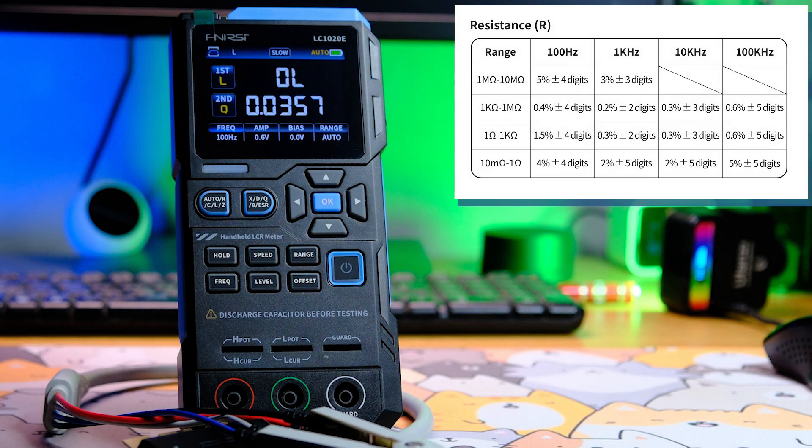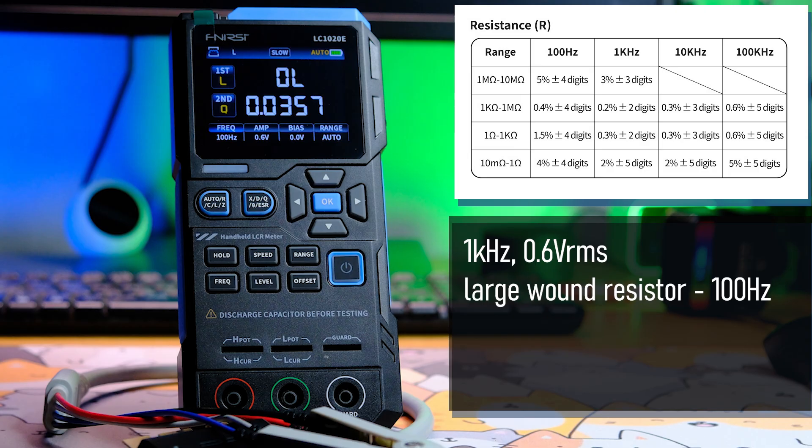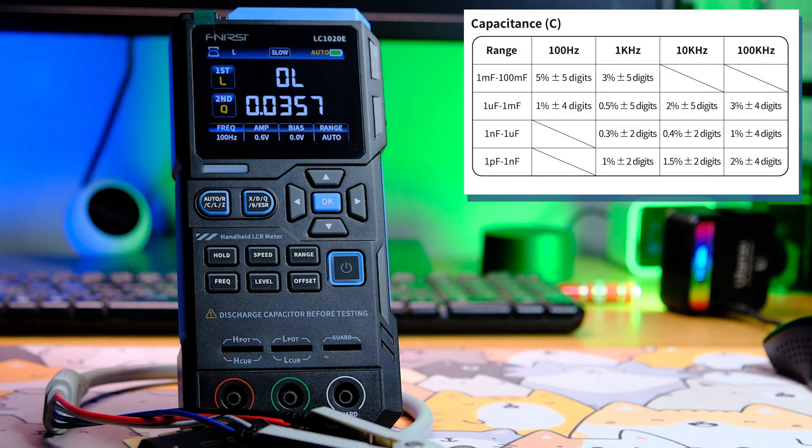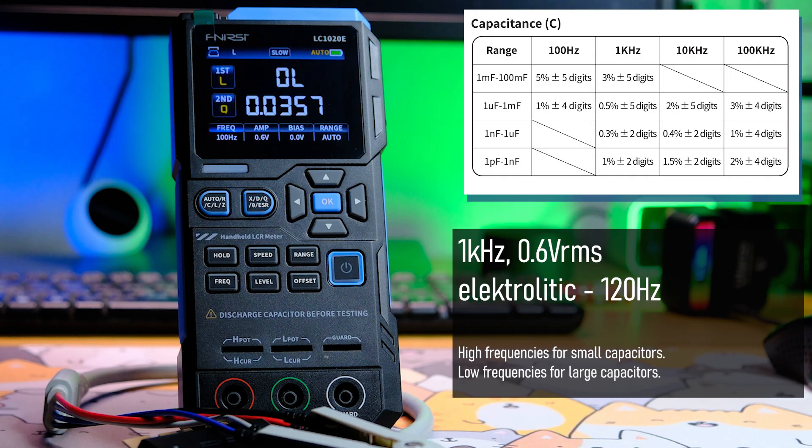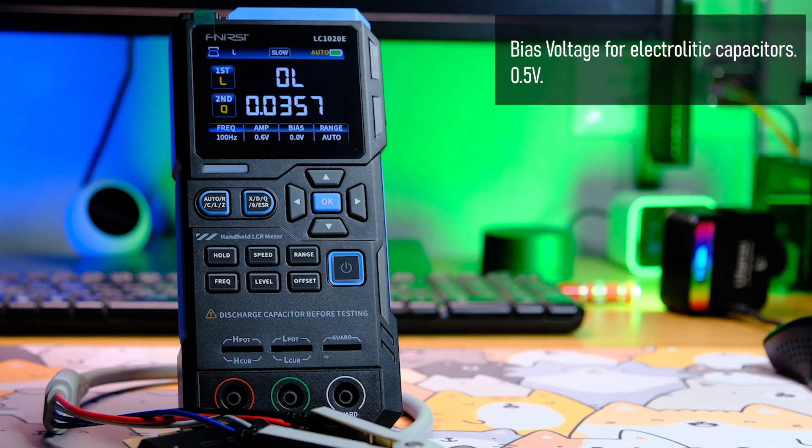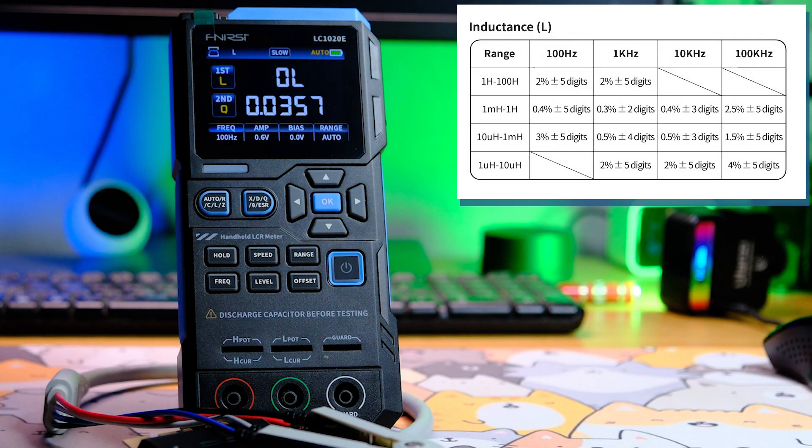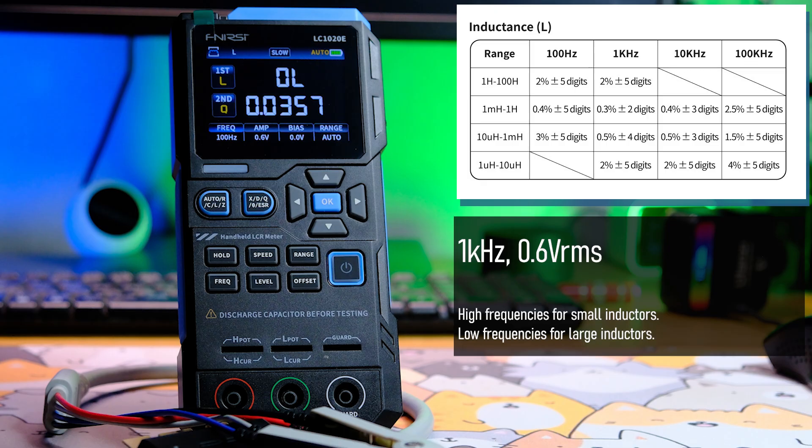Resistance measurements are recommended at 1 kHz with a signal amplitude of 0.6 volts. The range is 10 milliohms to 10 megohms with varying accuracy across ranges. Large wire resistors also have significant inductance, so they're best measured at 100 Hz. Typical capacitors are recommended to be measured at 1 kHz with 0.6 volts amplitude. Electrolytic capacitors are recommended at 100 to 120 Hz. The rule applies: high frequency for low-value capacitors, low frequency for high-value. The measurement range is from 1 pF to 100 mF. For electrolytics, you also use a 0.5 volts offset. Inductors are also measured at 1 kHz and 0.6 volts amplitude. The rule is the same: high frequency for small inductance, low for large. The measurement range is from 1 microhenry to 100 henry.